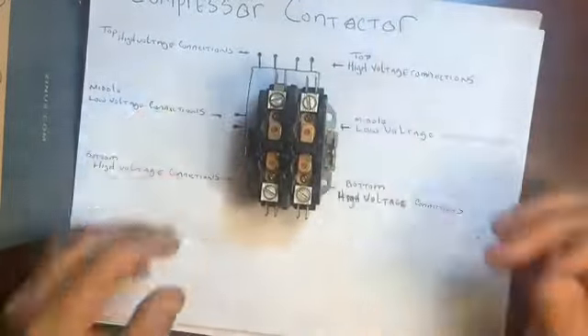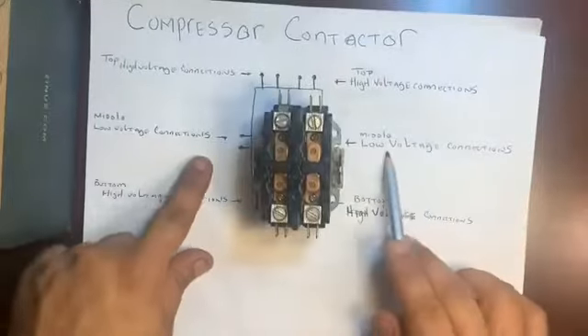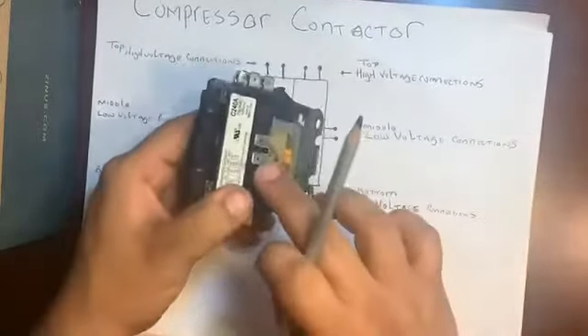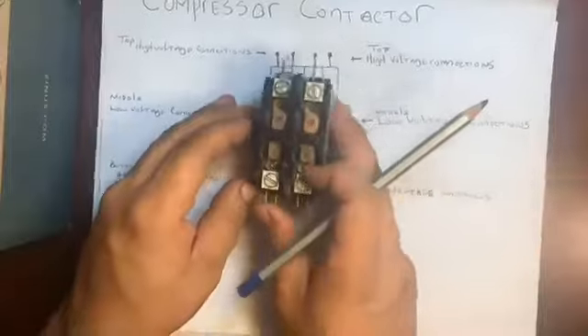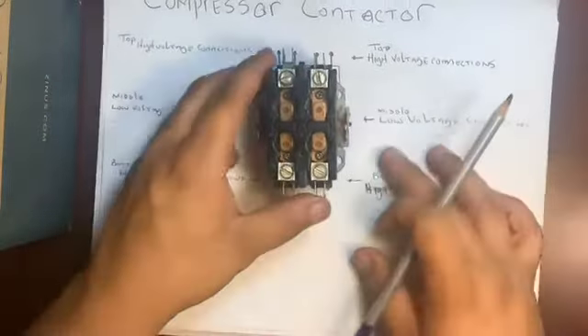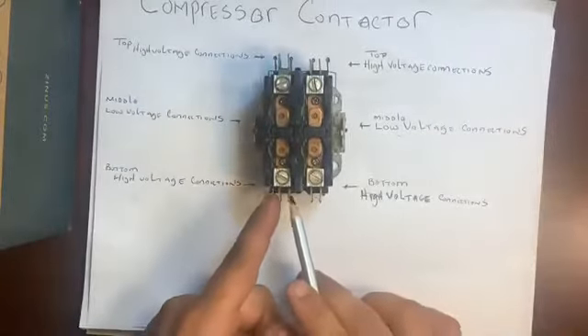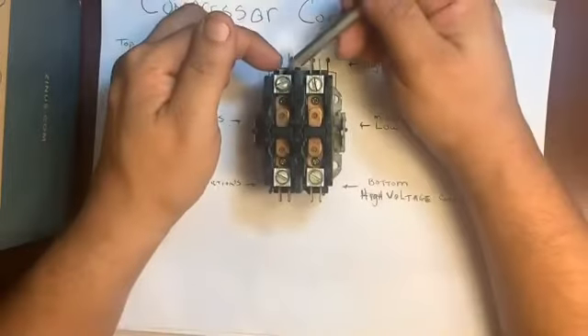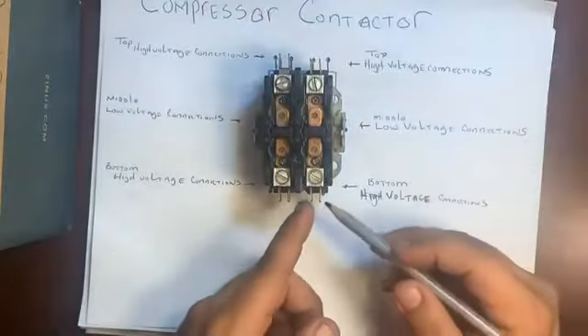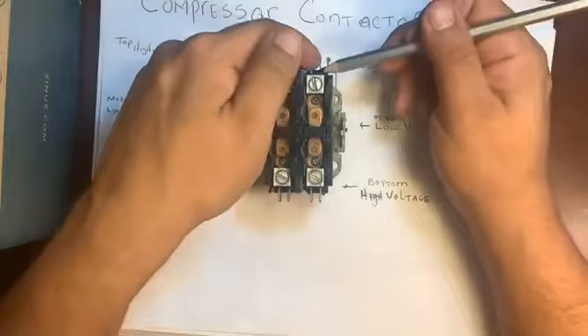How do they flow through? Because we have middle low voltage connections right here and right here. This is where the low voltage goes. And then your high voltage comes in through the bottom, 120 on L1, and it comes out the other side, 120. Comes in one side, 120, leaves out the top ones, 120.